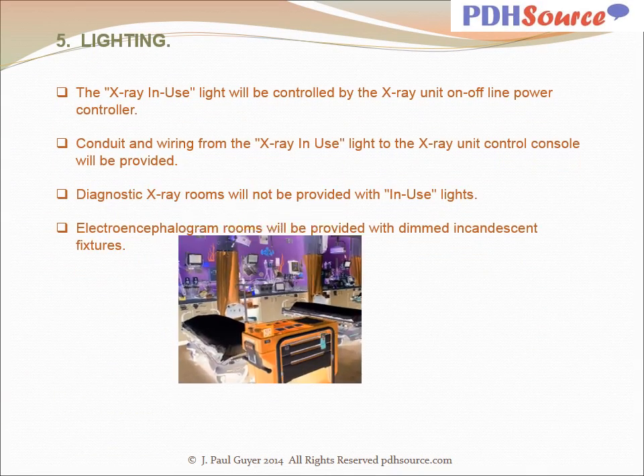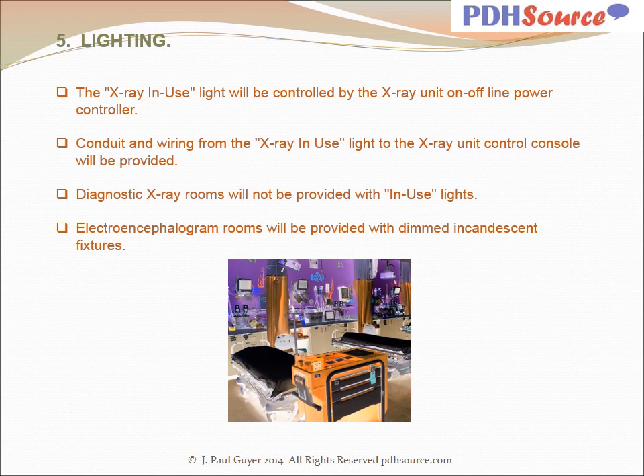The X-ray in use light will be controlled by the X-ray unit on-off line power controller. Conduit and wiring from the X-ray in-use light to the X-ray unit control console will be provided. Diagnostic X-ray rooms will not be provided with in-use lights. Electroencephalogram rooms will be provided with dimmed incandescent fixtures.